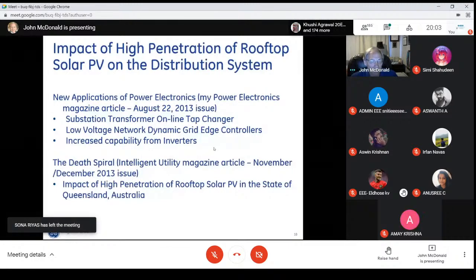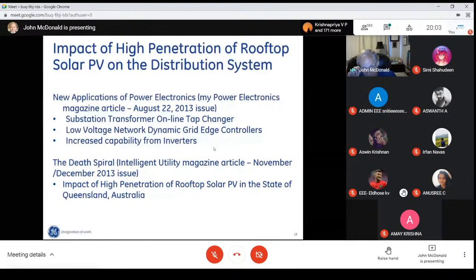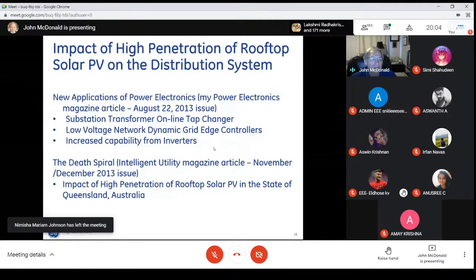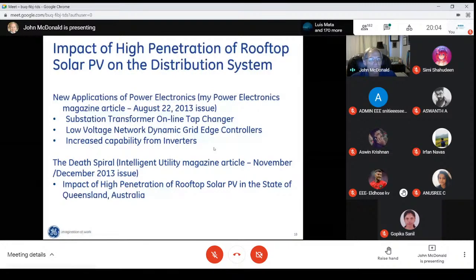has an online tap changer in a substation. That's mechanical, and the goal of the tap changer is to keep the secondary voltage constant. As the primary voltage fluctuates, the tap changer changes tap settings to keep the secondary voltage constant. It typically has 16 raise positions, 16 lower positions, and a neutral position, and each position change is a change of 0.5% of voltage.